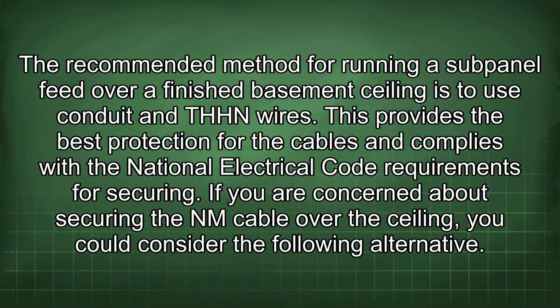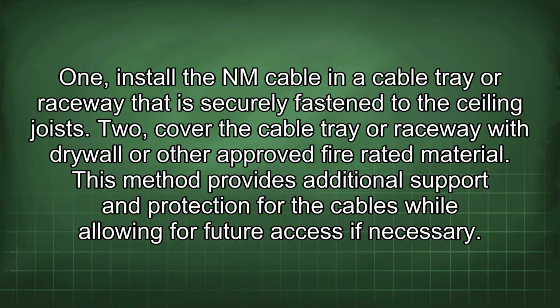The recommended method for running a subpanel feed over a finished basement ceiling is to use conduit and THHN wires. This provides the best protection for the cables and complies with the National Electrical Code requirements for securing. If you are concerned about securing the NM cable over the ceiling, you could consider the following alternative. 1. Install the NM cable in a cable tray or raceway that is securely fastened to the ceiling joists. 2. Cover the cable tray or raceway with drywall or other approved fire-rated material. This method provides additional support and protection for the cables while allowing for future access if necessary.